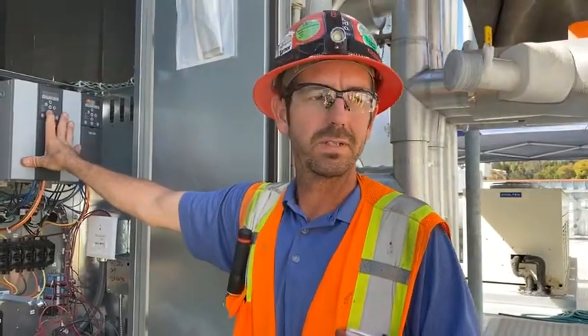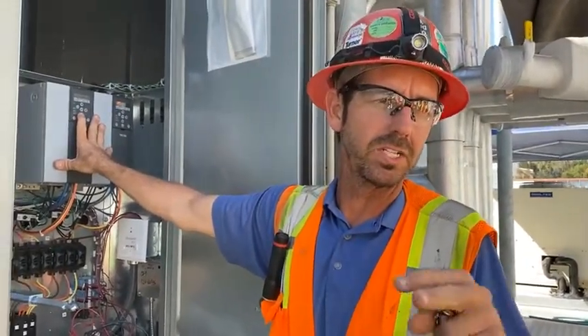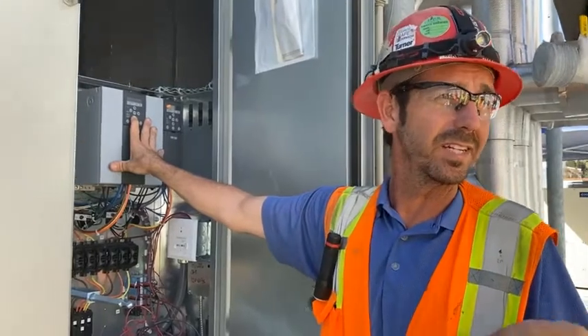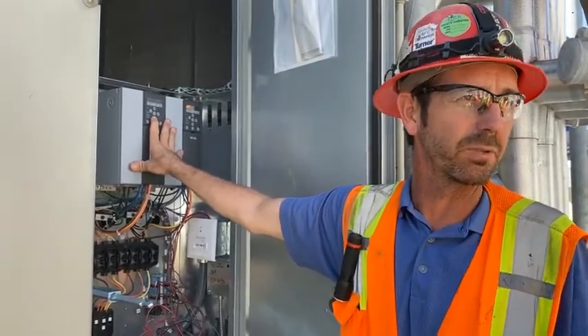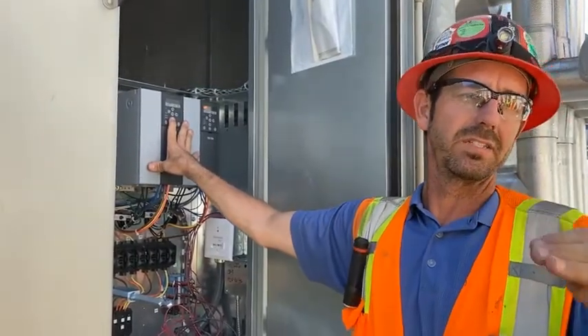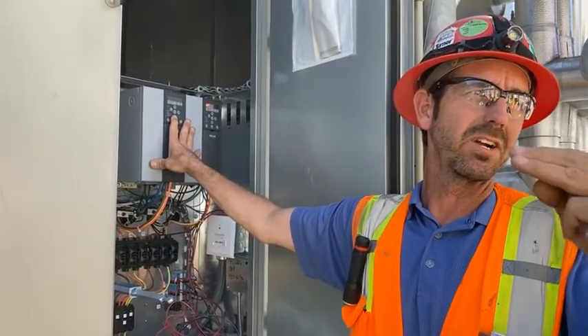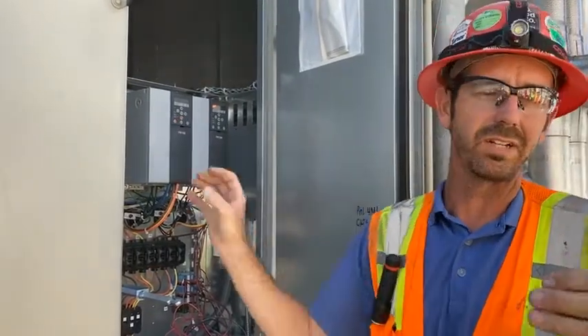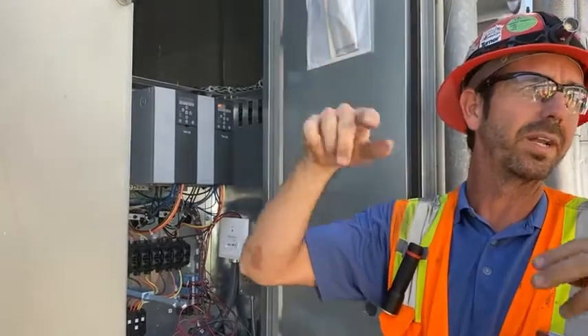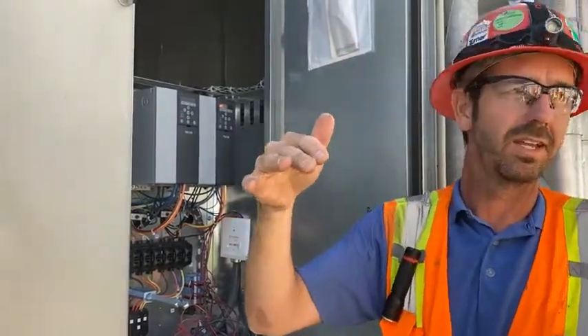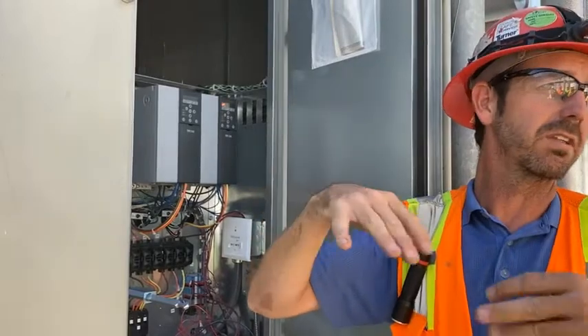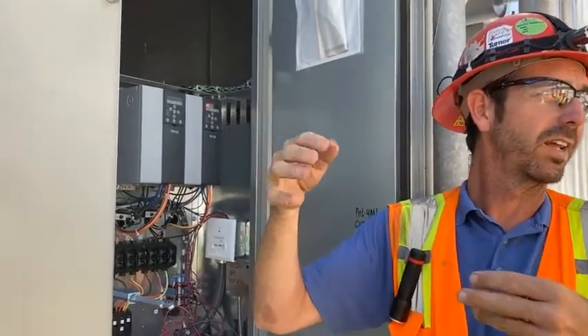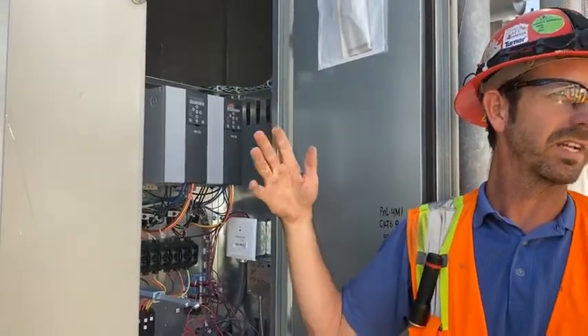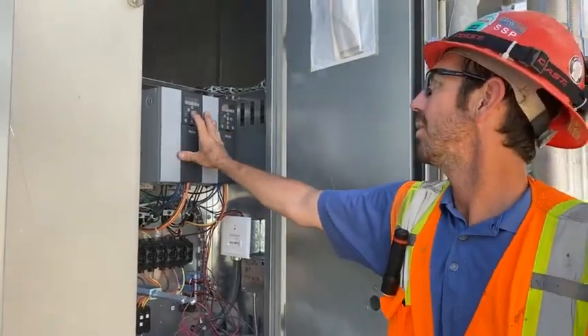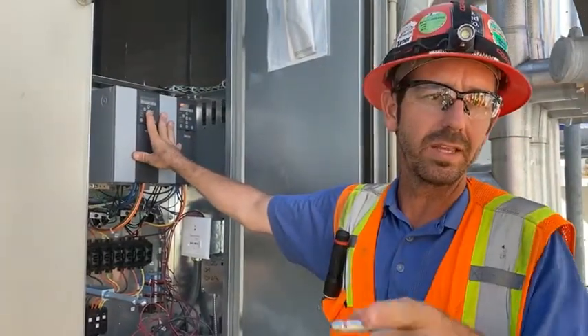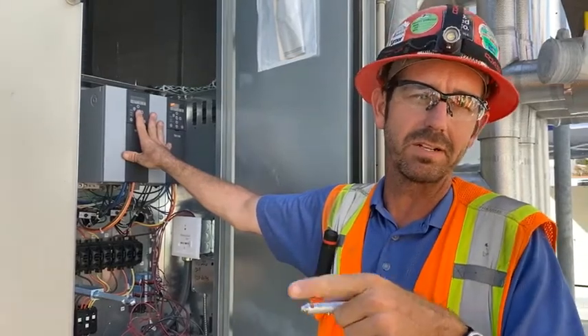Reference and ramps, that's how you would fine-tune the BMS guy's signal coming into the unit. So I've already worked with Doug. We've already verified that his 0-volt signal turns the unit off, and then as he starts increasing his 0 to 10 volt signal, it starts proportionally changing that output, and they're scaled properly. So it's 10 volts at 60, or it's the full hertz range, right? Again, I mentioned this is above 60 hertz. We'll get into that in a second. We want to make sure the reference and the max hertz match each other.